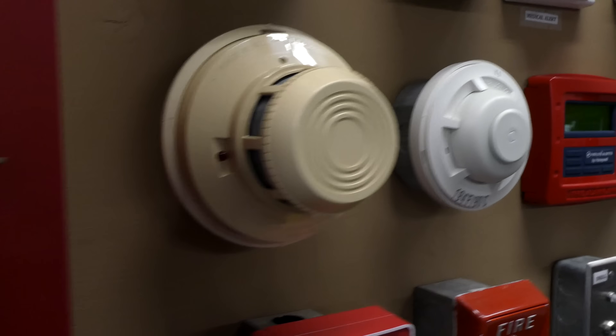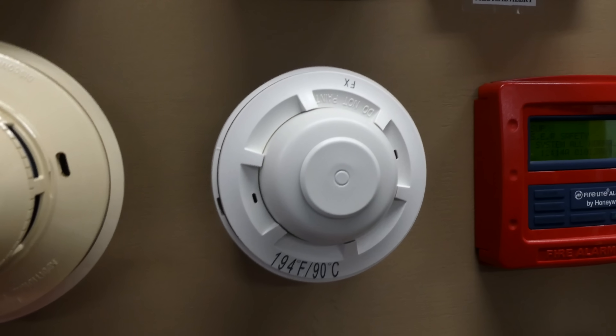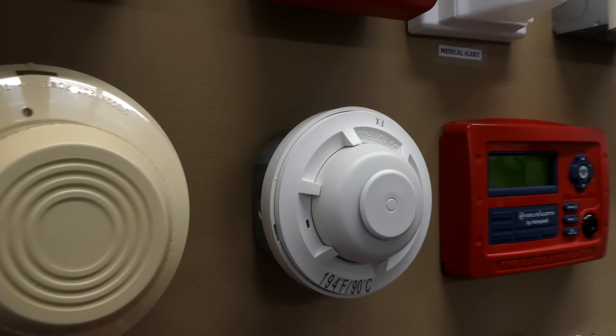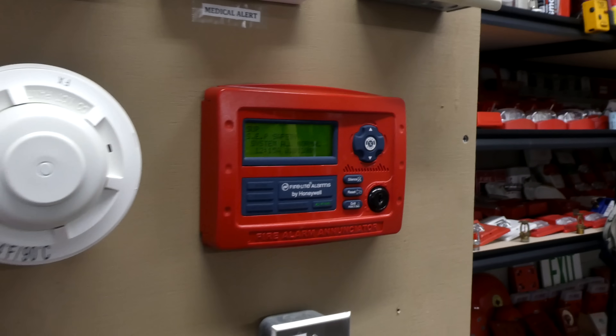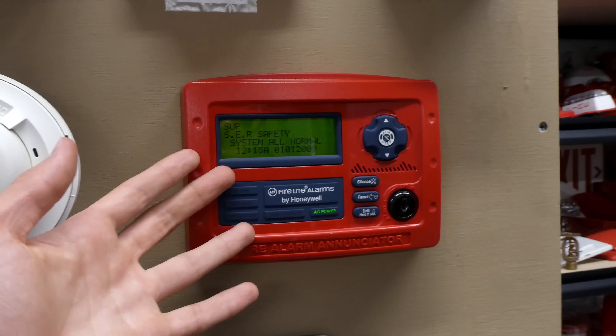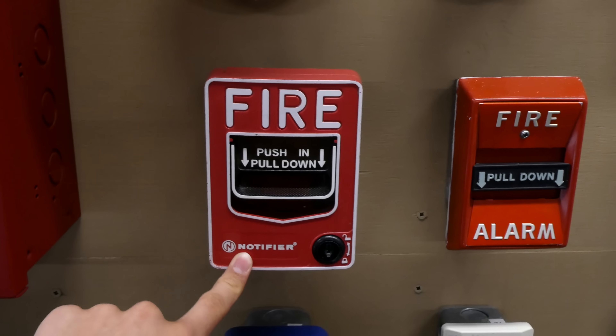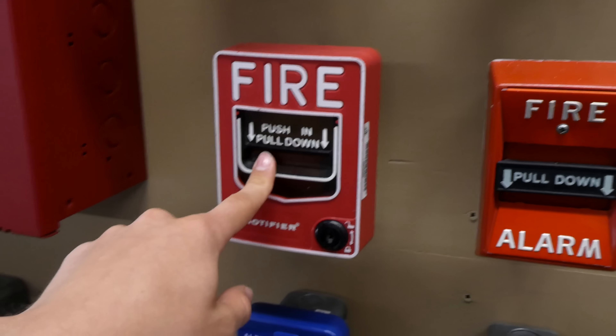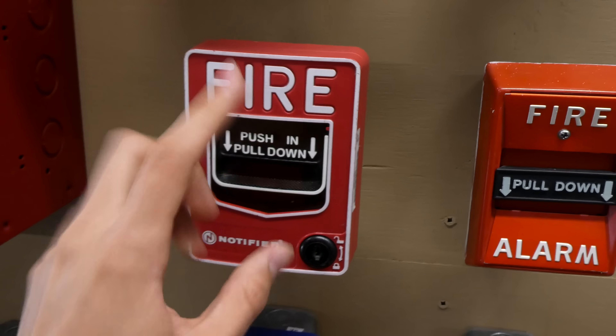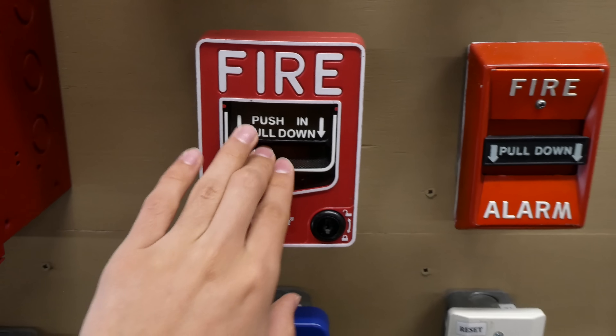Coming down here we have a System Sensor 2400 smoke detector, and then we have a System Sensor 5604 heat detector. Right here we have a Fire-Lite ANN-80 enunciator — this is basically a smaller fire alarm control panel. Then going down here we have a Notifier NBG12-LX; however, the LX part which makes it addressable is not being used — I just have it wired as conventional.